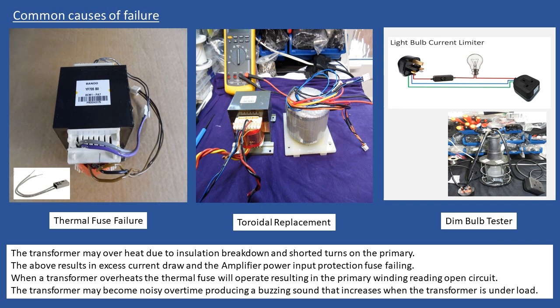Now, if we have maybe a domestic product, say a lawnmower, or a hairdryer, or even a shredder, those devices will have a thermal fuse, but those thermal fuses will be resettable. So if the thermal fuse reaches its cutoff temperature, so maybe it's 120 degrees, it will operate, it will go open circuit, it will prevent the current flowing through, but once the device cools, it will reset. Not in the case of the transformers, it doesn't happen.